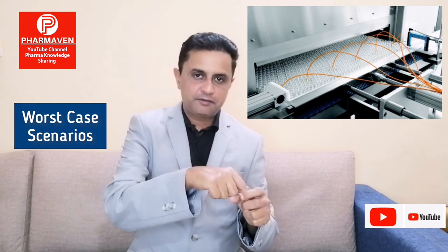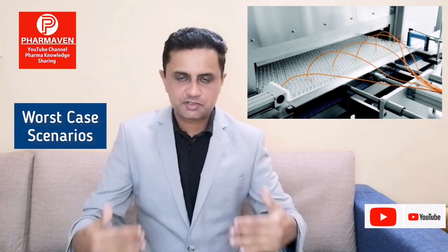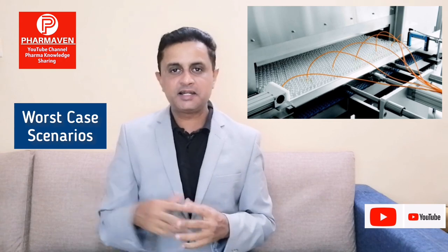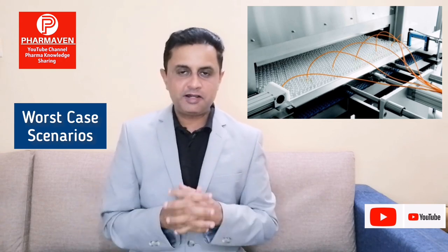So we can tie the vials inside the hole with Teflon tape and put the sensor inside. Then the entire jig can be kept in between. So it will travel through the vial mass smoothly, without the vial getting toppled or the sensor getting pulled. This requires a lot of effort, and more than one person has to be involved in allowing the thermocouple to go inside the tunnel conveyor in a smooth way.